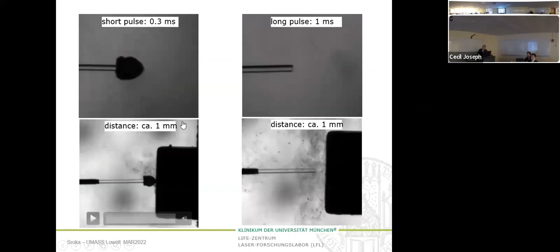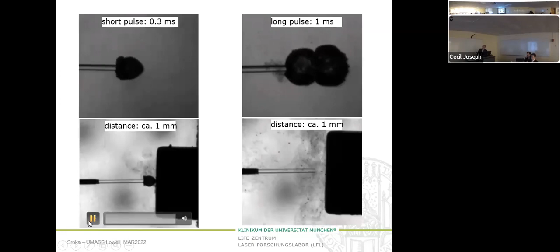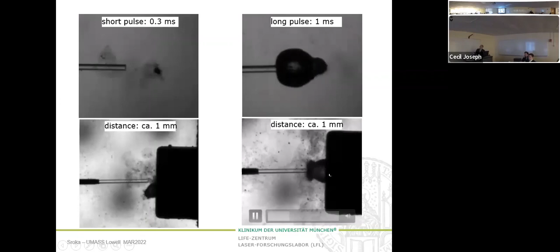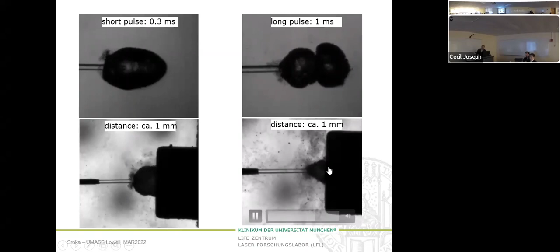This is a bubble of 300 microseconds, and this is a bubble of 1 millisecond. You can clearly see the length is much more than here. And this is in free water. And if we do it with a target, this is a Begostone target, and you can clearly see how it works here. And here you have enough time during this millisecond to apply a lot of energy directly into the water in the pores of the stone for this tiny ablation possibility.